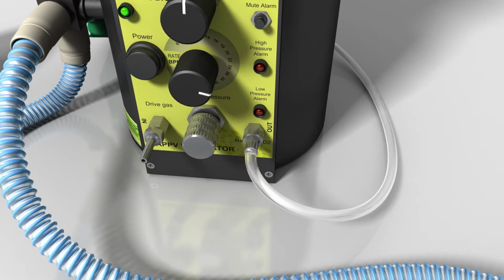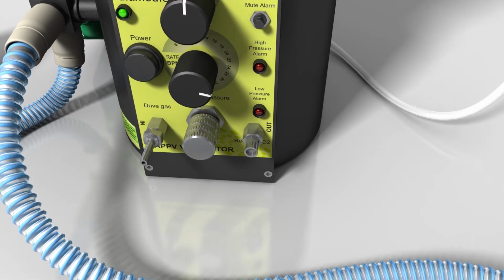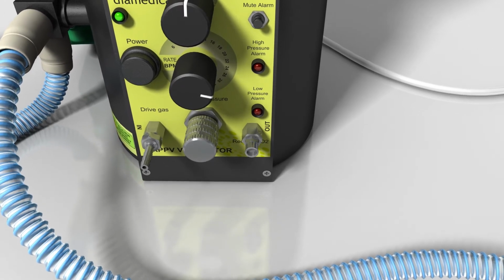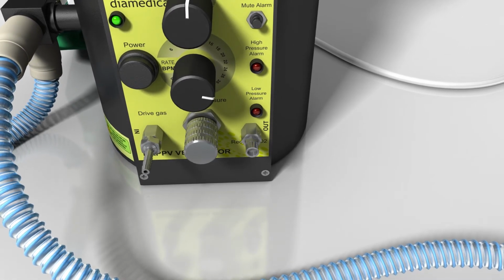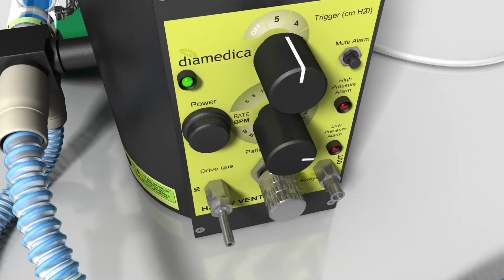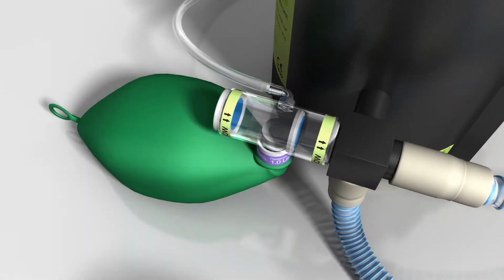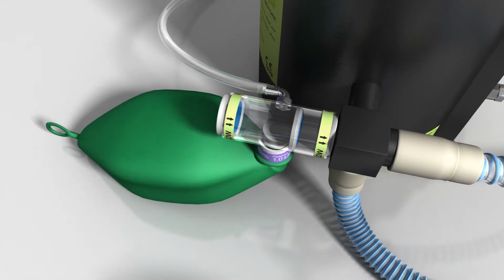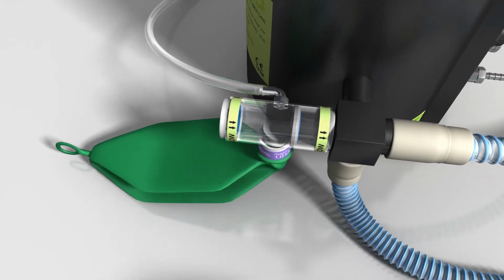Additional oxygen can be added to the inspiratory valve by disconnecting the recycled gas from the ventilator and connecting it to a supply from a suitable oxygen source. A 1-litre reservoir bag is fitted to the bottom of the circuit block to store oxygen during the expiratory phase of ventilation.